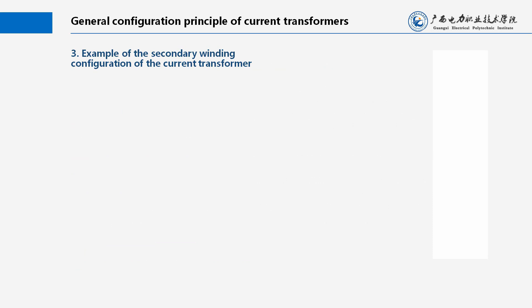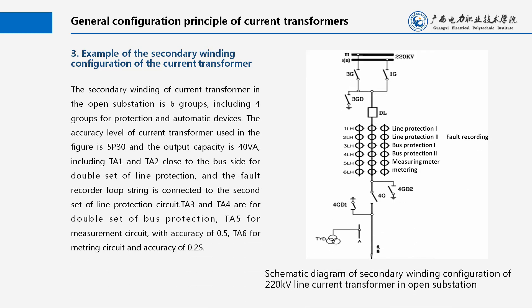Example of the secondary winding configuration of the current transformer: The secondary winding of the current transformer in the open substation is 6 groups, including 4 groups for protection and automatic devices. The accuracy level used is 5P30 and the output capacity is 40VA. TA1 and TA2 close to the bus side are for double set of line protection, with the fault recorder loop connected to the second set of line protection circuit. TA3 and TA4 are for double set of bus protection, TA5 for measurement circuit with accuracy of 0.5, and TA6 for metering circuit with accuracy of 0.2S.